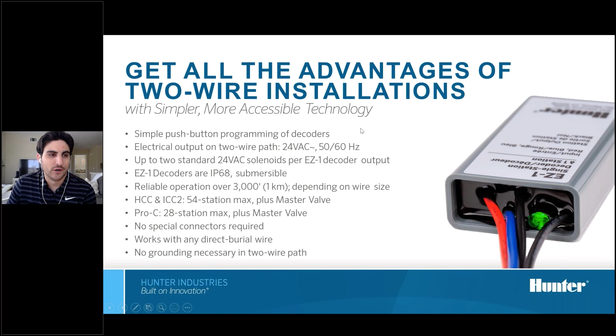Ben, I just want to point out real quick too that we say no special connectors and no special wiring and stuff like that, but if you're already doing 2-wire and doing it well, I always recommend specifying the standard for 2-wire systems and not dumbing it down too much. It does cost a little more for those connectors, but we don't want you to forget everything you learned necessarily. We just want to let you know that this system has been tested in the worst conditions of wiring and the worst condition of wire connectors, so it will work. But always follow the best guidelines and best management practices when you're installing or even specifying a 2-wire system.